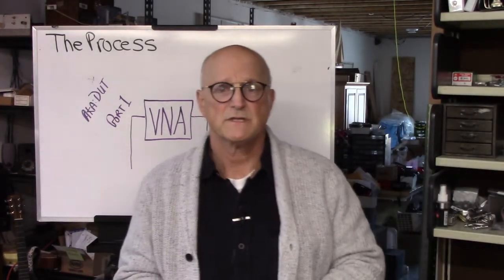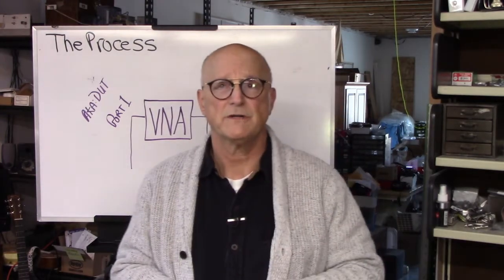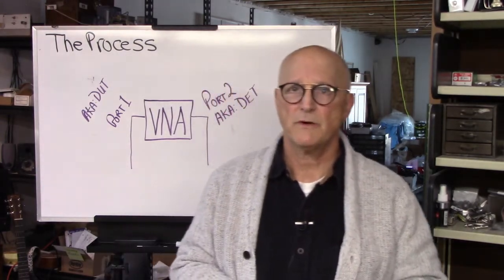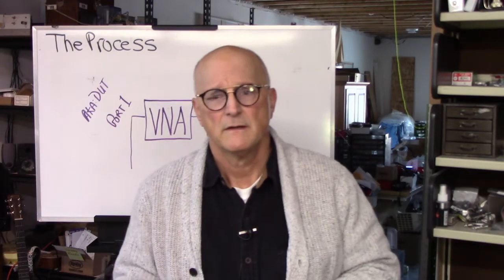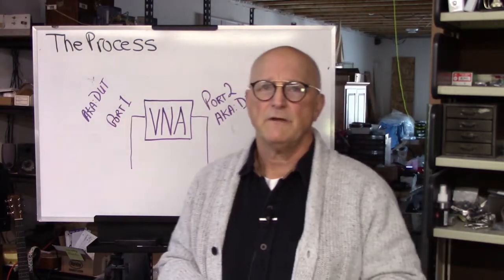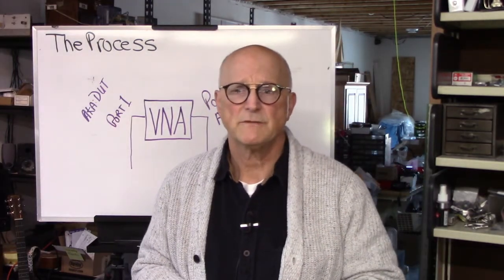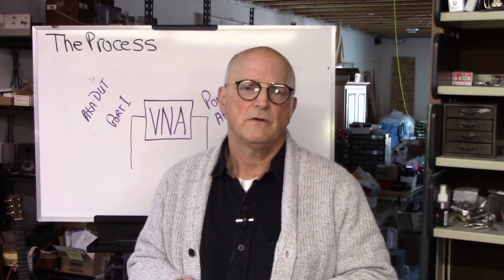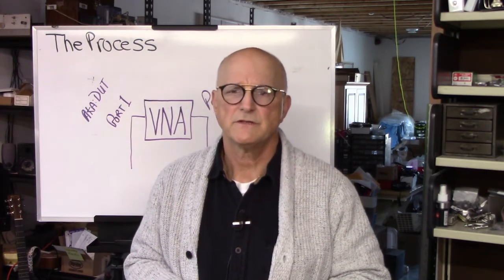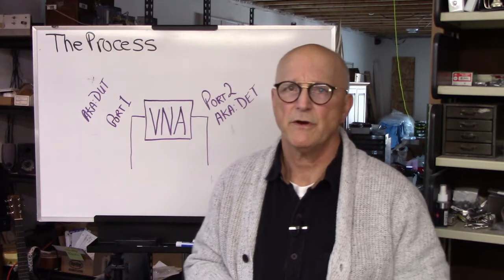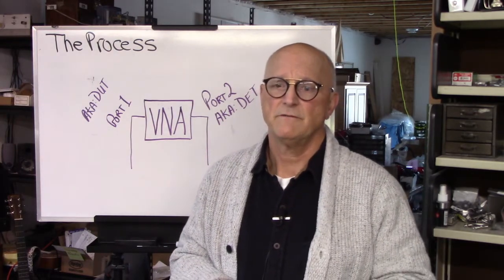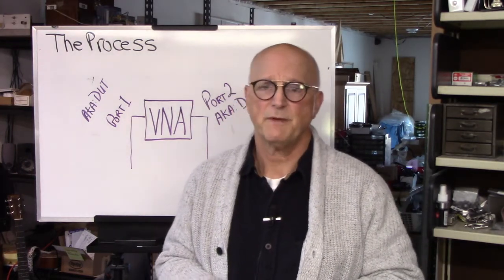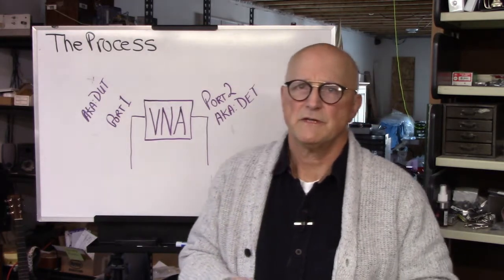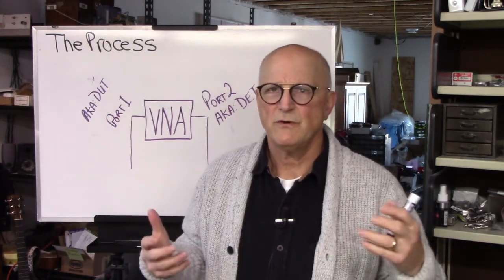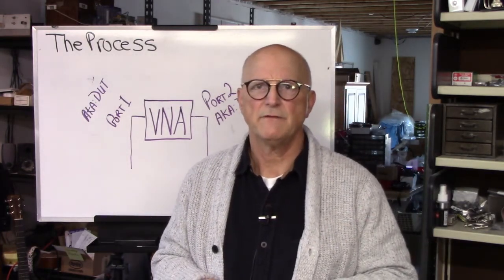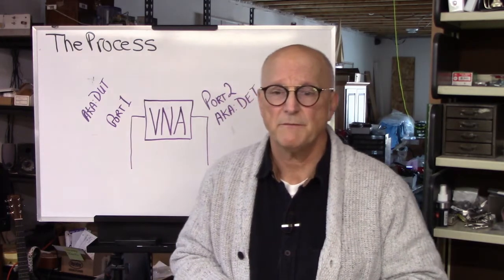And so let's now step through the calibration process for a 2-port calibration. Now, to calibrate your VNA for a particular measurement, you may need known-to-be-good standards to do that, and laboratory quality standards of this type can be very expensive. But for the sake of what we often do, we don't need to have that kind of expense associated with it.